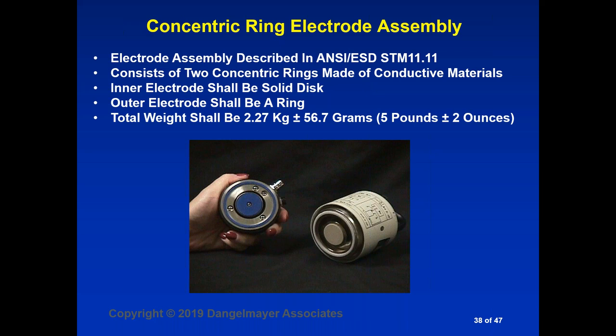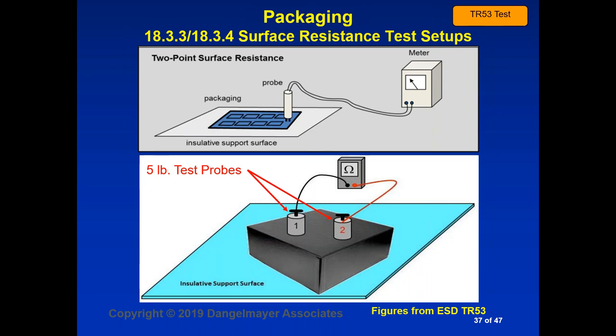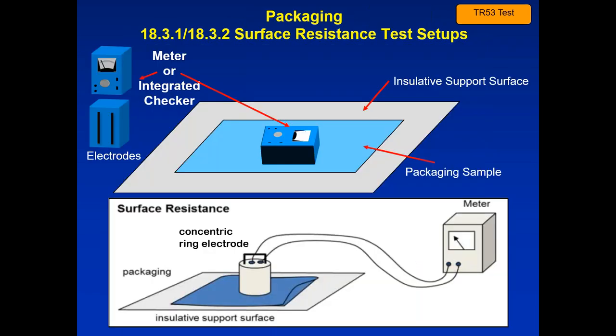One of the problems we had, if you remember that first meter we looked at on the top here, is that very often this checker does not have a 5-pound weight, and sometimes it makes inaccurate measurements. The standards all specify that the measurement electrodes should be a 5-pound weight unless you're using a 2-point probe.